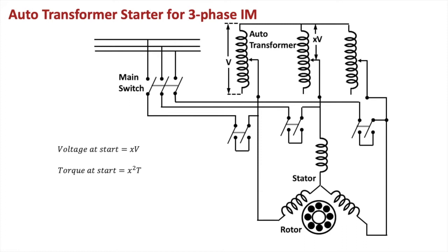But the disadvantage of auto transformer starting is that the initial torque decreases because torque is proportional to the square of the voltage. So a small voltage means the torque will also be reduced proportionately. The auto transformer is connected to a parallel switch; at starting we give a lesser voltage, and when we apply the rated voltage, the auto transformer is cut out from the supply system and is no more in the connection. The motors are connected directly to the main supply, because the auto transformer is only required for the starting of the motor.